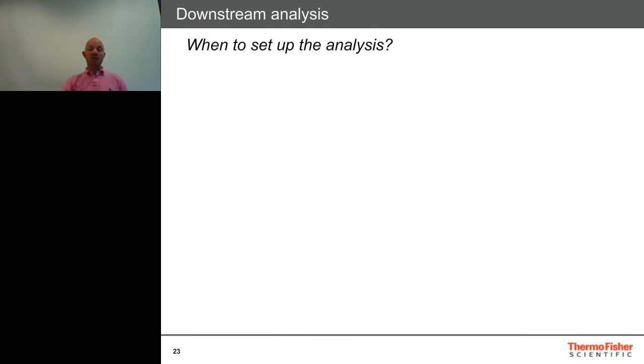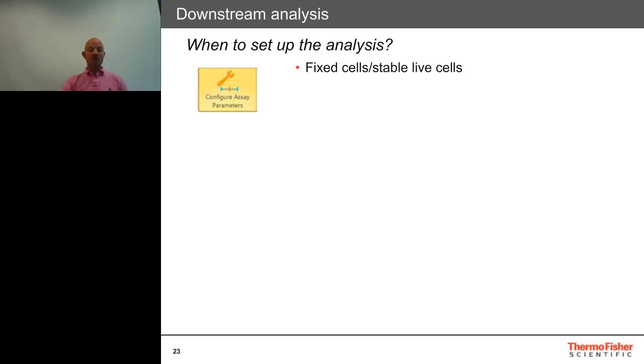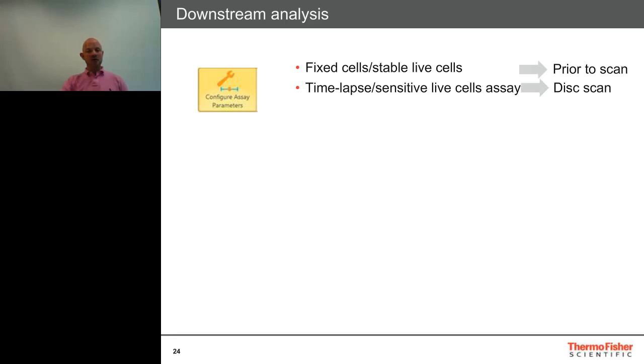When thinking about analysis, it's important to consider when we'll set it up. If we're using fixed cells or living cells with a stable reporter where processes won't be changing much during acquisition, we can set up the analysis prior to the scan — segmenting cells and identifying objects using just a few representative images taken from the plate. However, for time-lapse imaging or very sensitive rapidly-changing reporters, we can acquire images only and then go back and do a disk scan, reanalyzing the acquired images from the hard disk. This is called a disk-based scan and is a way of speeding up acquisition times.